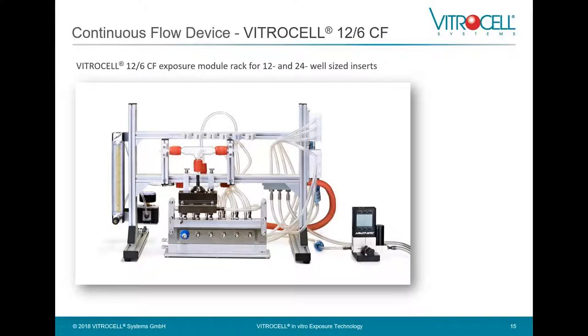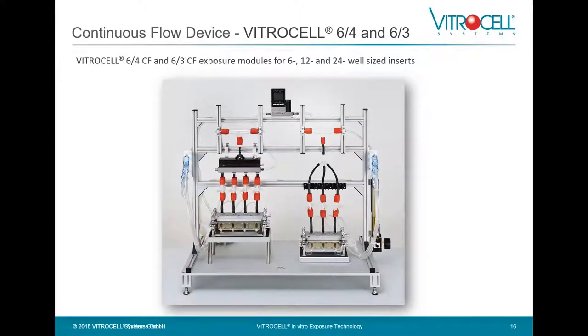Here is an example of a smaller installation: one compact module with six compartments, where three compartments are exposed to the atmosphere and three are exposed to clean air, providing a control for cellular reaction. This device is suitable for 12 and 24 well-sized inserts. On a larger scale, for the six-well format, there are two separate modules — one for exposure and one for clean air — forming a universal platform compatible with six, 12, and 24 well-sized inserts.